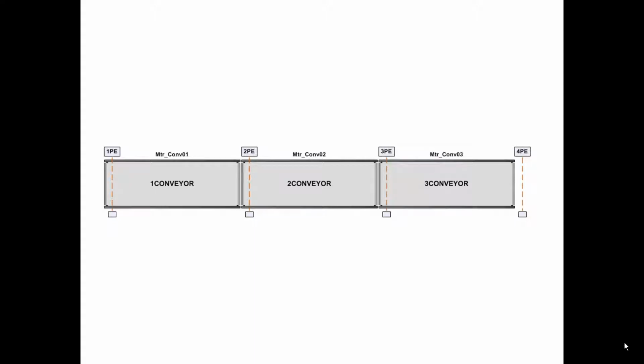We want system start and system stop push buttons that enable the conveyors to run, enable only, not run, or disable them from running. This does not actually start and stop the conveyors directly, just enables or disables the ability to start the conveyors. So you have 2 different types of start stops here, one for the conveyors and one for the system.